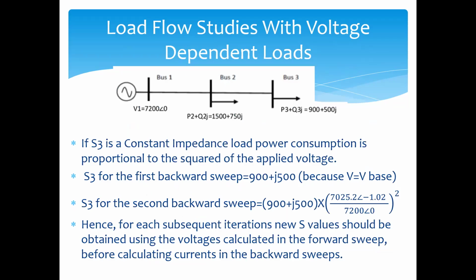Next, what will happen to the load flow studies when we have a constant impedance load? Here, the load power consumption is proportional to the square of the applied voltage. So, for the calculation of S3 for the first backward sweep, it is the same because V equals V base. For the second backward sweep, we need to calculate using this expression. So in all subsequent iterations, new S values should be obtained using the voltage calculated in the forward sweep before calculating the current in the backward sweep.